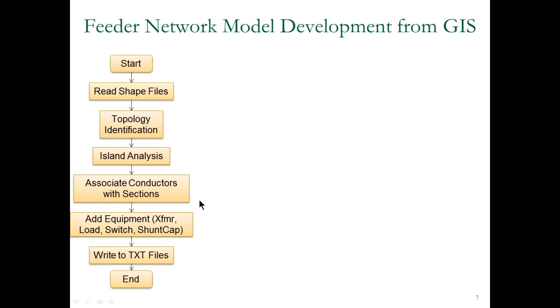The next step is to link all the lines and cables in the feeder to their line type and cable type that we defined in the conductor library that I described in the previous slides. Similarly, all the other equipment like the transformers, switches and shunt caps are also associated to their respective equipment library. So after all of these steps, we have the full model in MATLAB. The next step is to write the corresponding text files in a format suitable for either OpenDSS or CYMDIST, so that we can run power flow analysis in those tools.